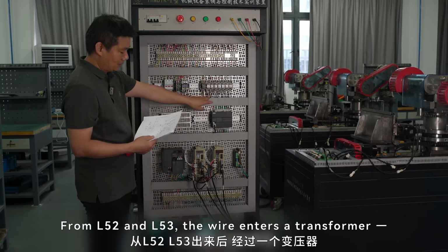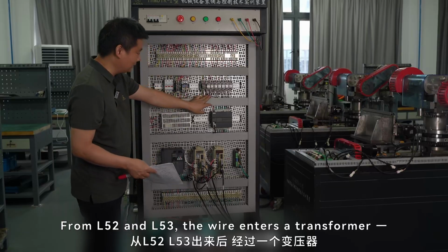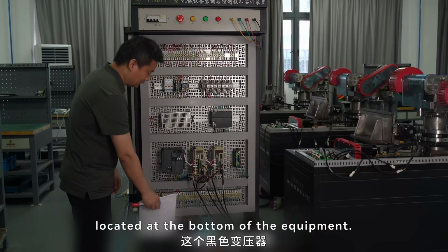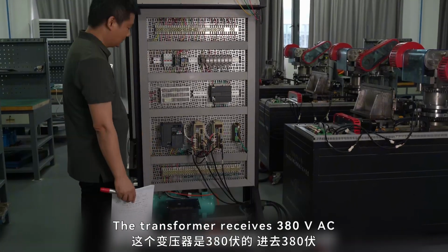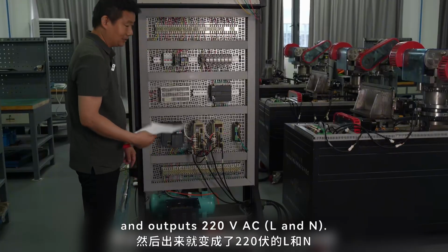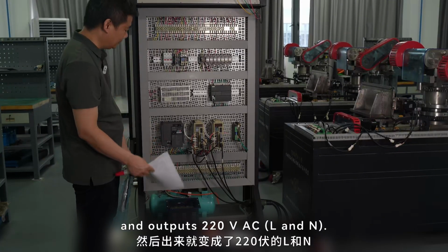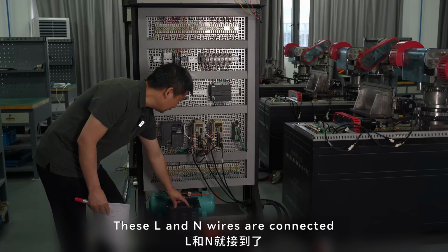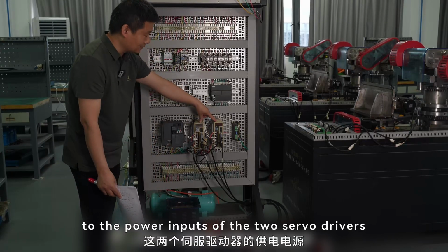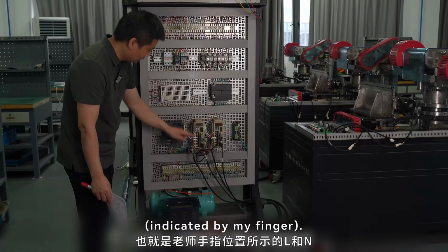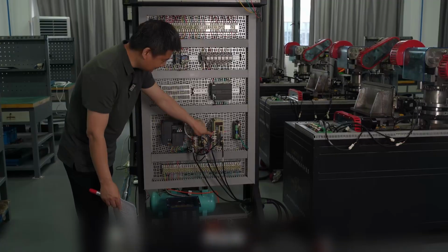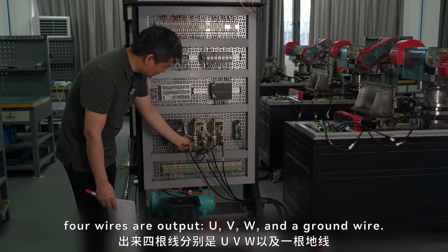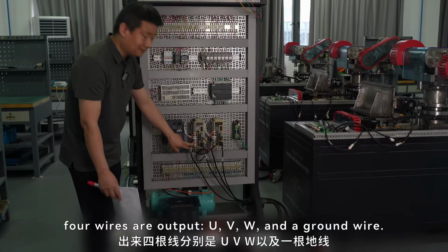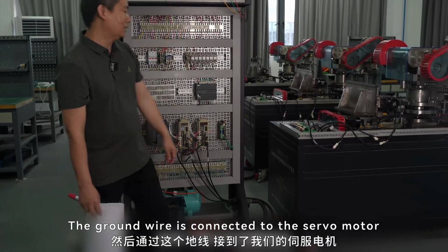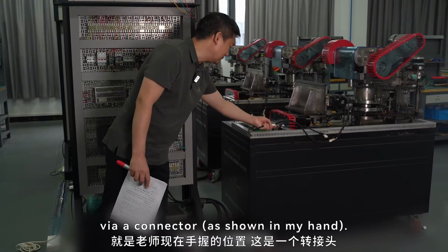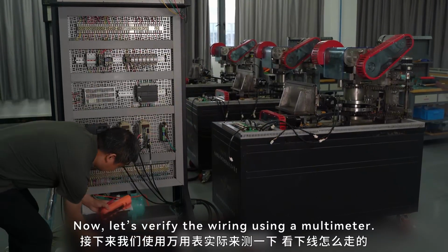From L52 and L53, the wire enters a transformer, the black transformer located at the bottom of the equipment. The transformer receives 380 volts AC and outputs 220 volts AC, L and N. These L and N wires are connected to the power inputs of the 2 servo drivers, indicated by my finger. After conversion by the servo driver, 4 wires are output: U, V, W, and a ground wire. The ground wire is connected to the servo motor via a connector, as shown in my hand. Now, let's verify the wiring using a multimeter.